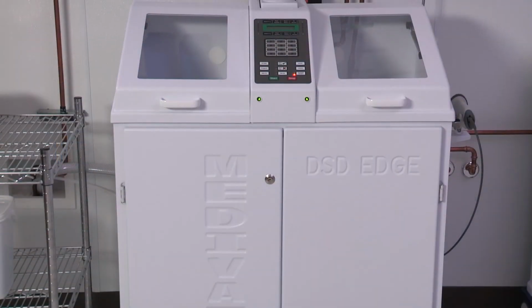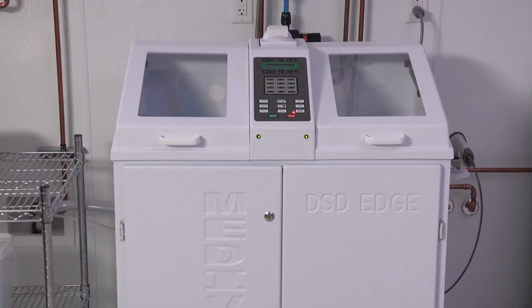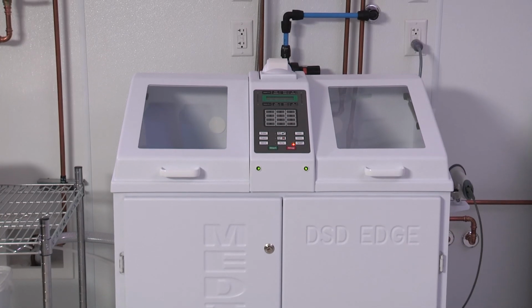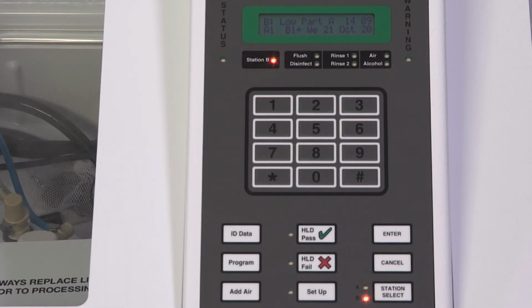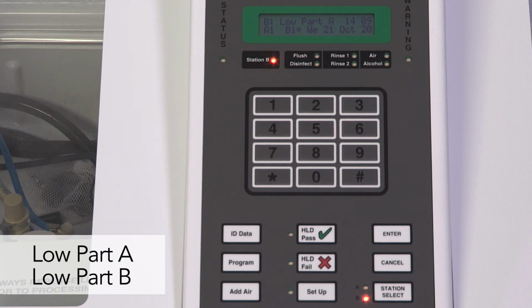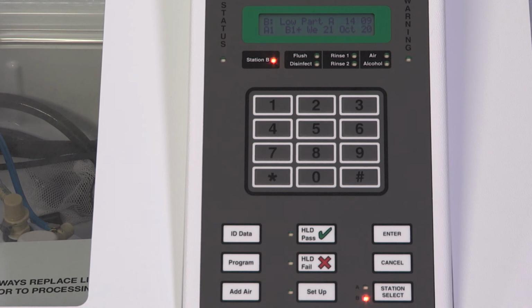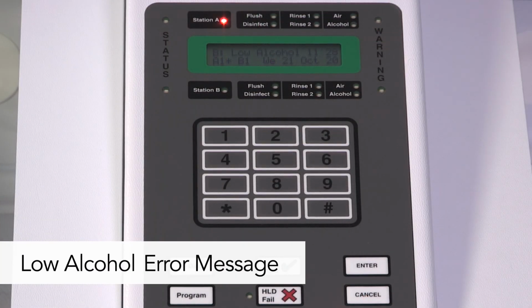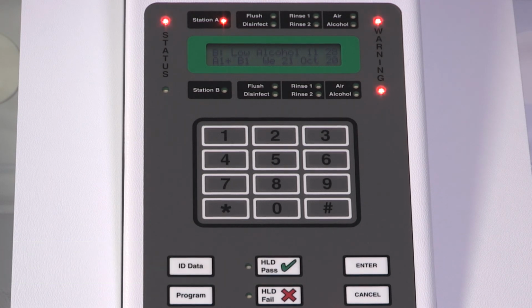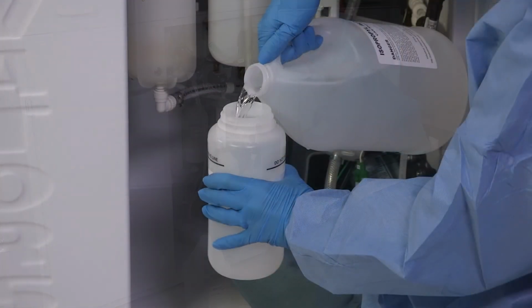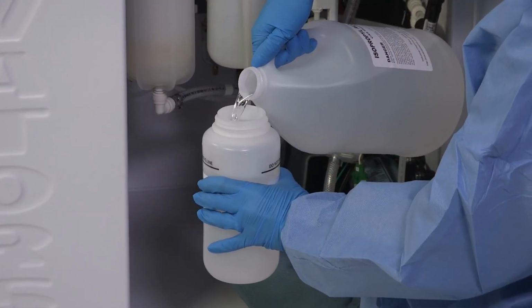In this segment, we will discuss how to troubleshoot some common messages or errors you might encounter. If a disinfectant container is low or needs to be replaced, the display will show low part A, low part B. Always replace both part A and B containers at the same time. If the alcohol is low or empty, the unit will stop, alarm, and the status and warning lights will flash. Remove, refill, and replace the alcohol reservoir.